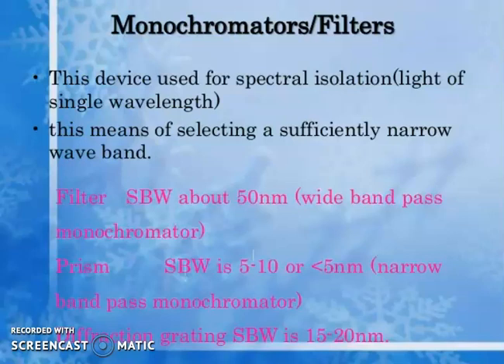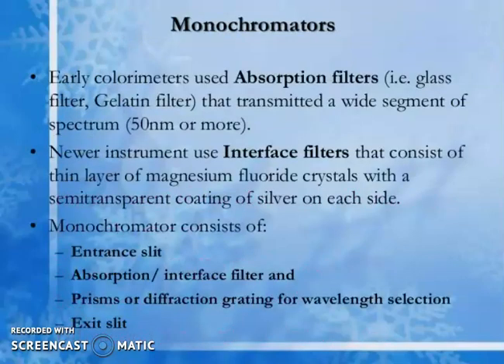Monochromator or filter: this device is used for spectral isolation of light of a single wavelength by selecting a sufficiently narrow waveband. Types include: filter (SBW ~50 nm, wide bandpass monochromator), prism (SBW 5–10 nm or less, narrow bandpass monochromator), and diffraction grating (SBW 15–20 nm).